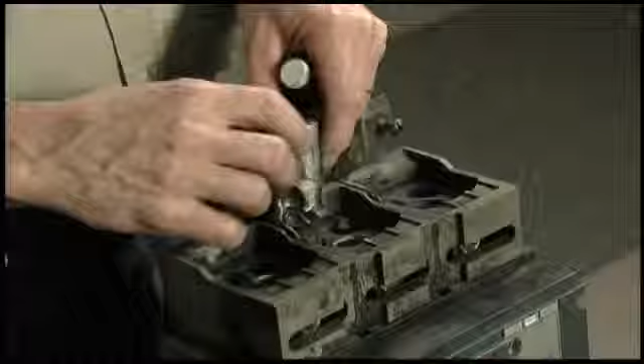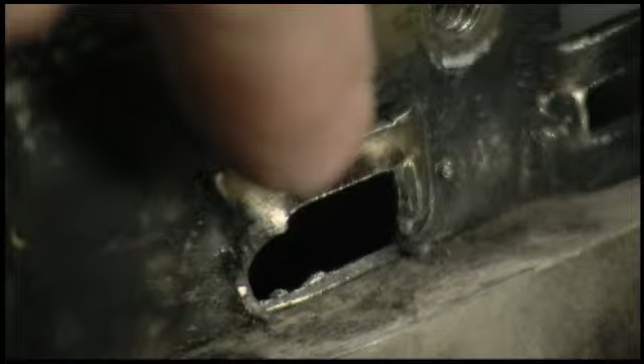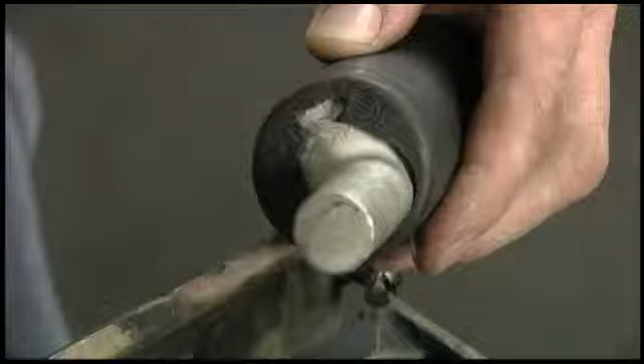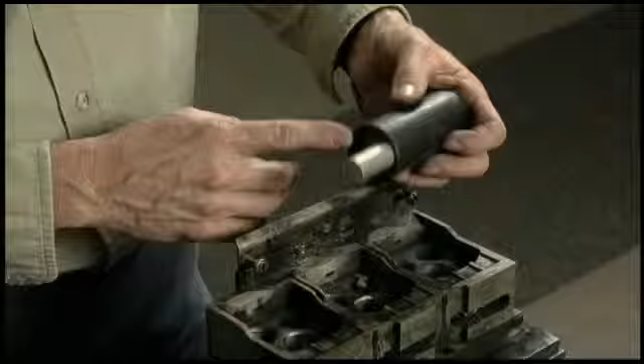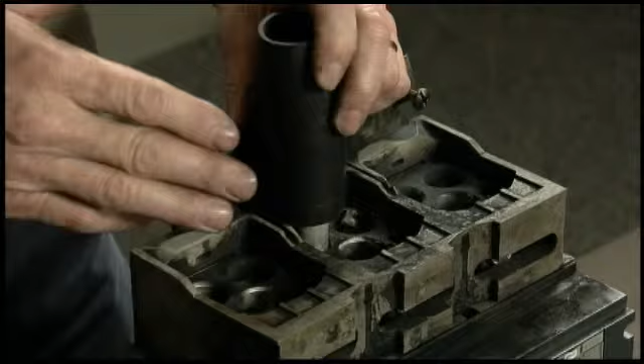We started looking at the breaker and components to figure out what actually happened. Apparently they were struggling with it when they installed it, and you can see that when they put it in, this sharp component right here had cut into the boot on the insulator. So when they inserted the lug into the breaker and tightened it down, even though we tested it to make sure there weren't any grounds there, either the stress from turning on the breaker or the energy available jumped that gap in there and created the arc flash.